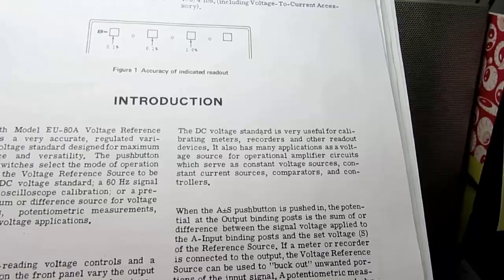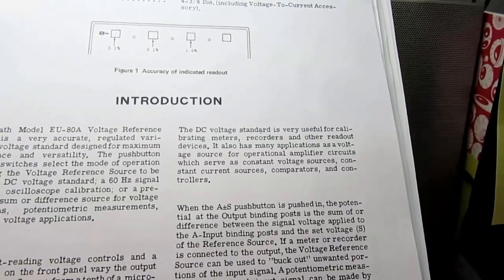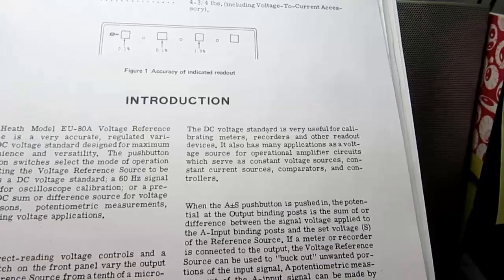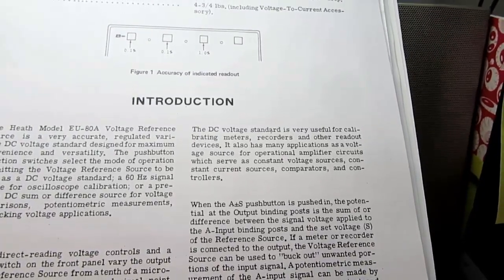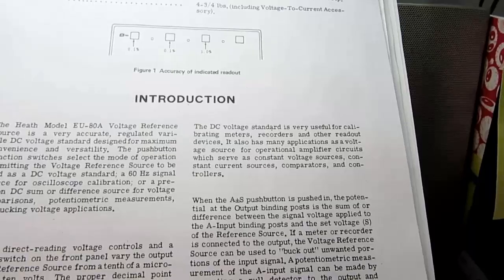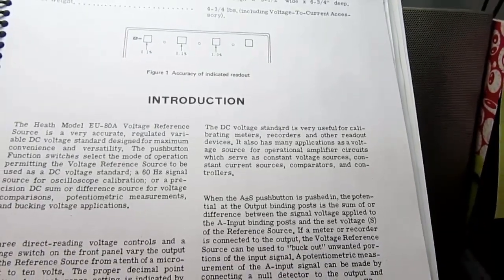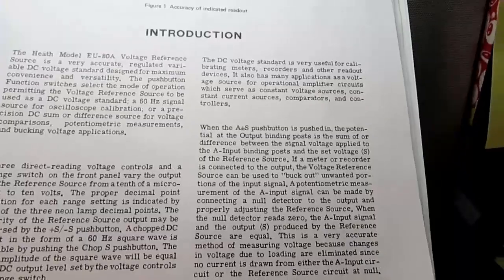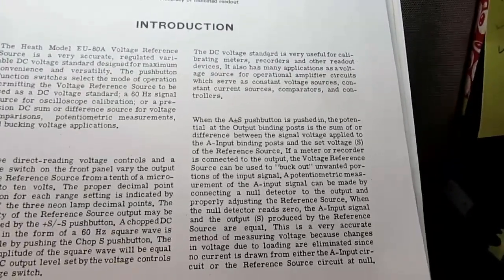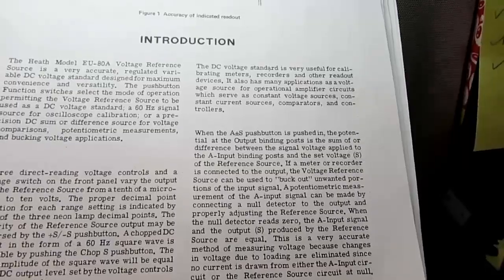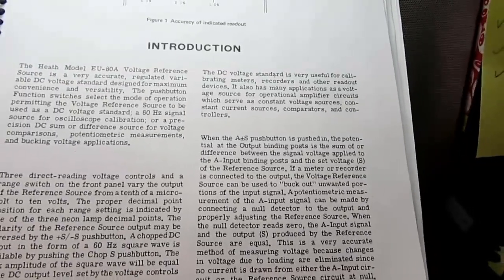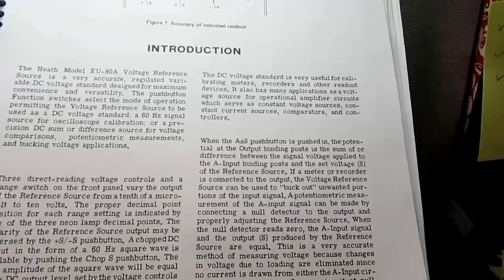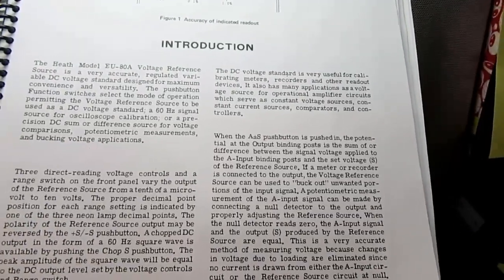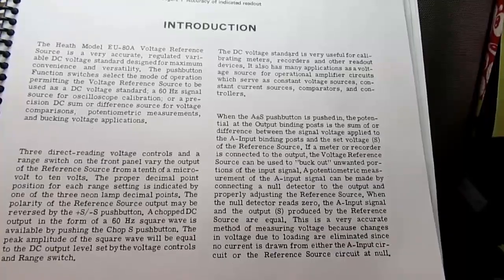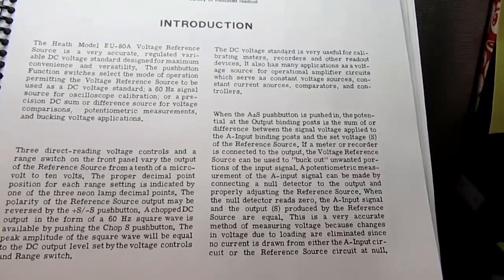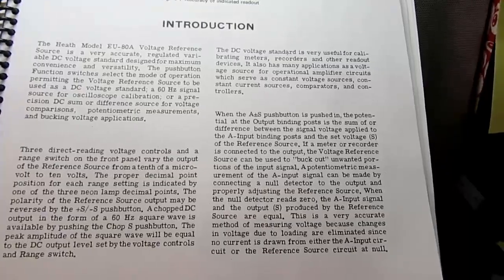The DC voltage standard is very useful for calibrating meters, recorders, and other readout devices. It also has many applications as a voltage source for operational amplifier circuits, which serve as constant voltage sources, constant current sources, comparators, and controllers. When the A plus or minus S push button is pushed in, the potential at the output binding post is the sum of or difference between the signal voltage applied to the A input binding posts and the voltage you've set for the reference source. If a meter or recorder is connected to the output, the voltage reference source can be used to buck out unwanted portions of the input signal.